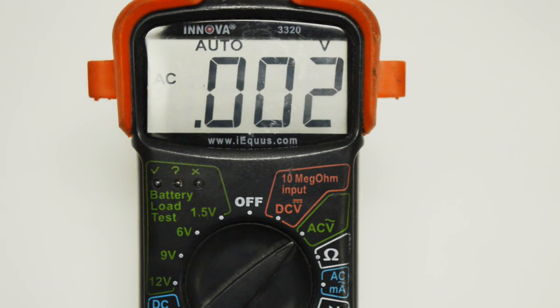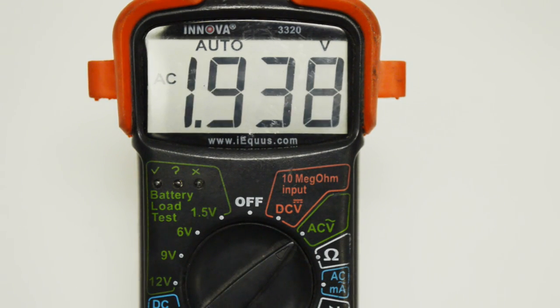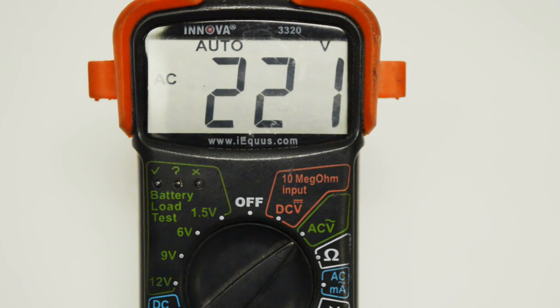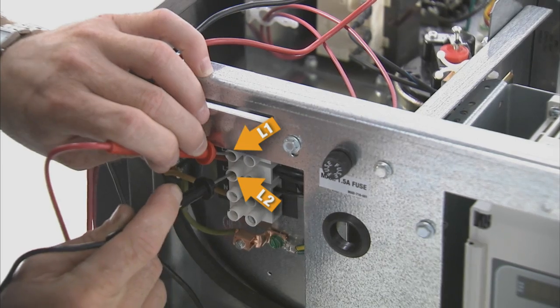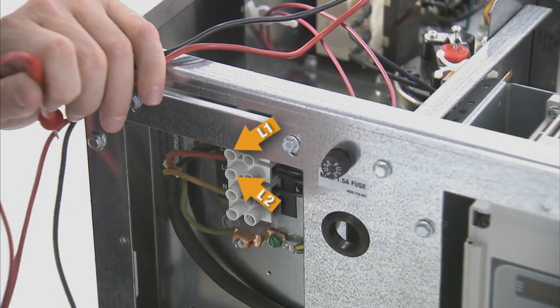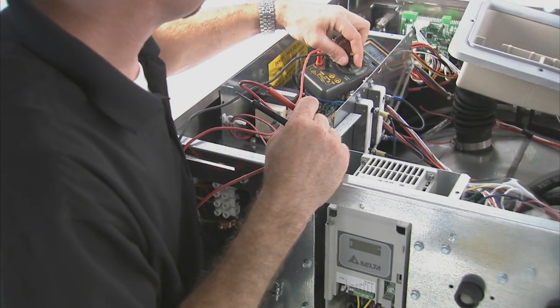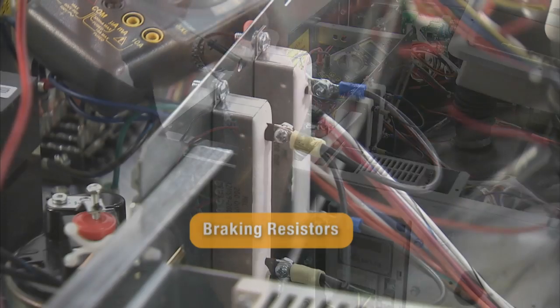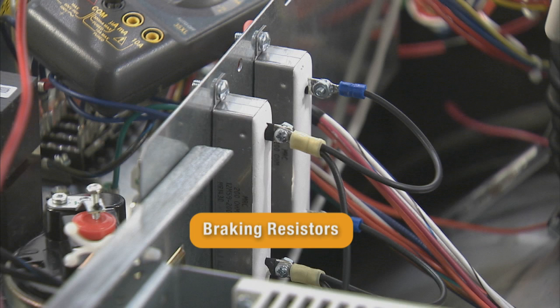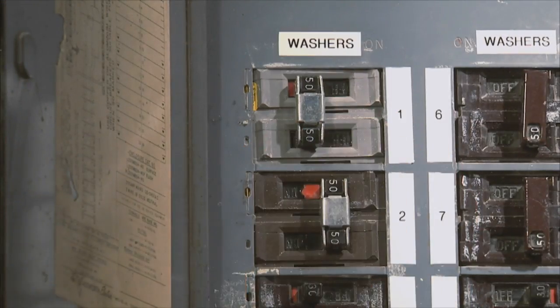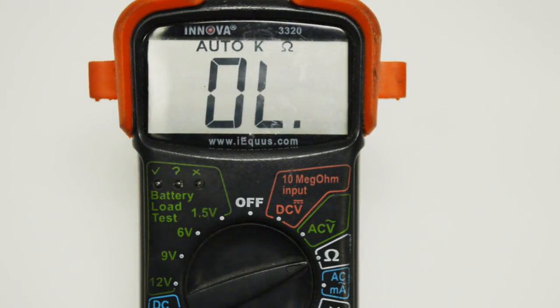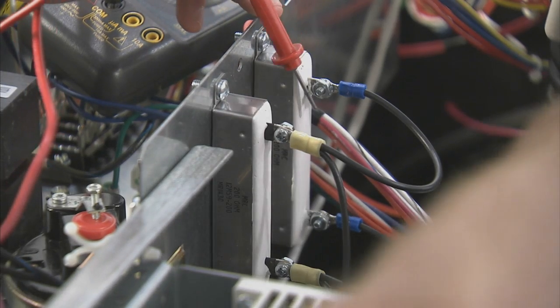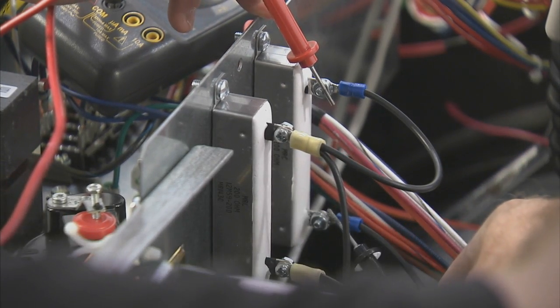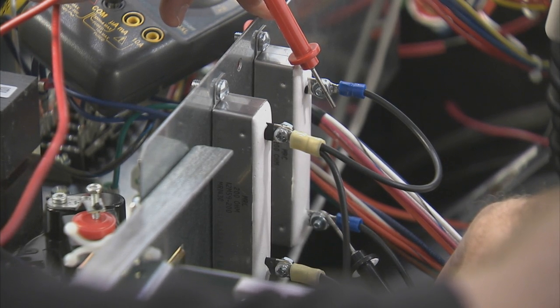The incoming voltage should be 208 to 240 volts AC. If the total voltage is lower than 208 volts or higher than 240 volts, consult a certified electrician to correct the issue. The next step is to check the resistance of the dynamic braking resistors. To do a resistance check of the braking resistors, make sure the machine is powered off. Using a voltmeter on the ohms resistance setting, put the red lead on one connection of the braking resistor and the black lead on the opposite connection of the same braking resistor.